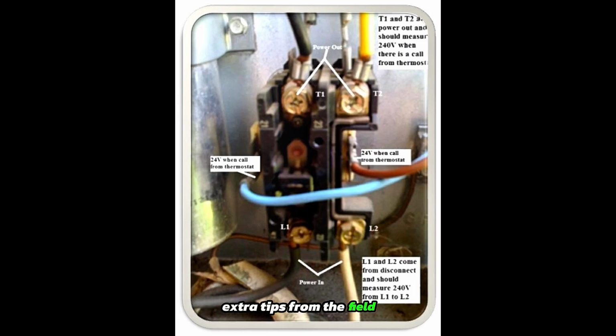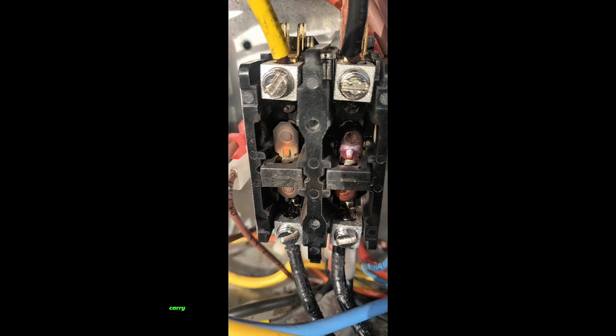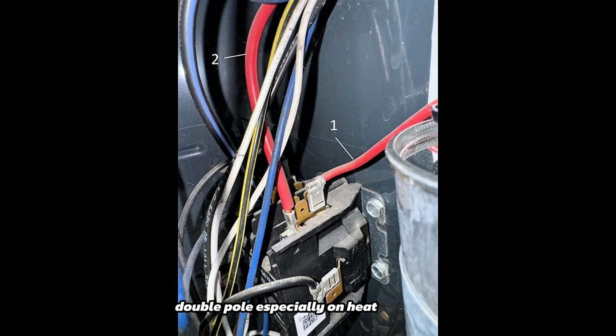Extra tips from the field. Always verify coil voltage. Some are 24 volts, others are 120 volts or 240 volts. Contactor coils burn out from power surges. Carry spares. Never reuse a stuck contactor. It may stick again. Label your wires before disconnecting. Watch for dual contactors, double pole, especially on heat pumps.